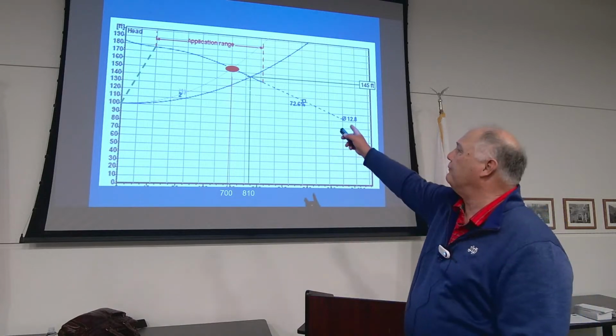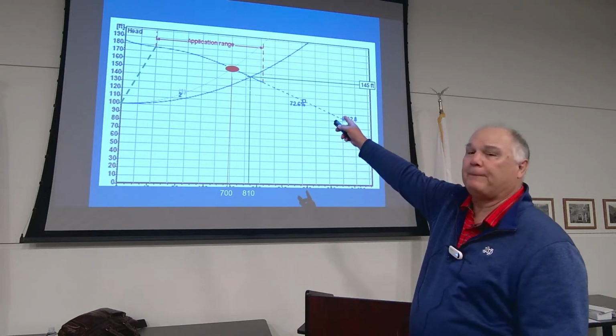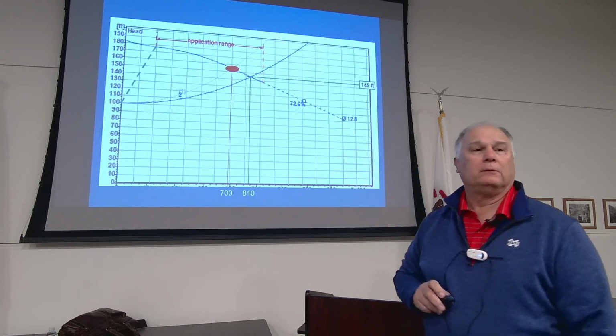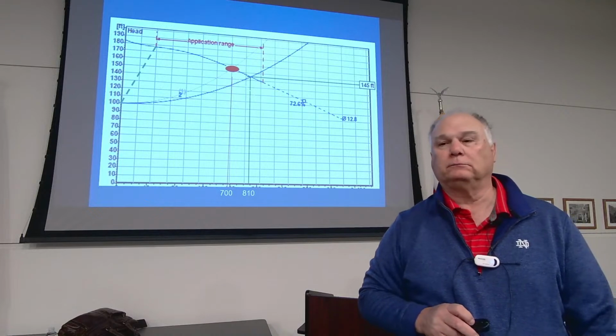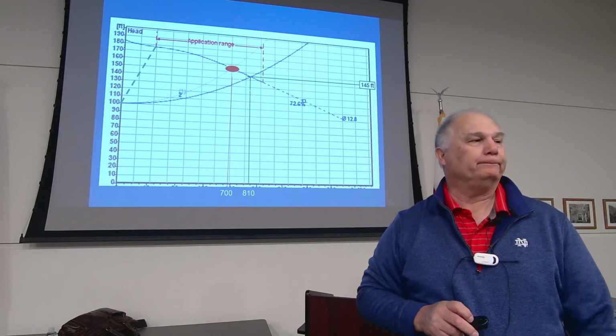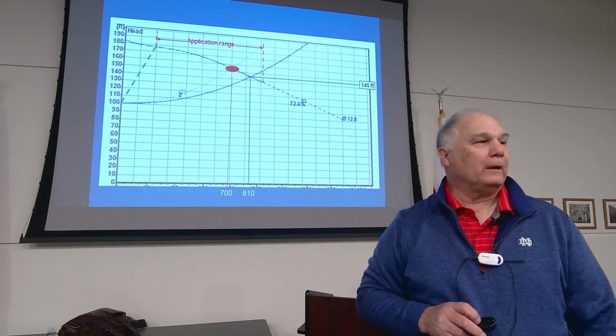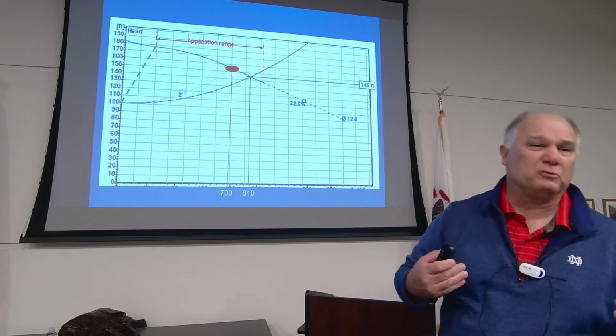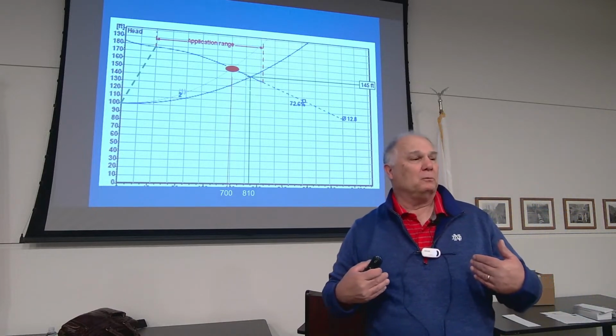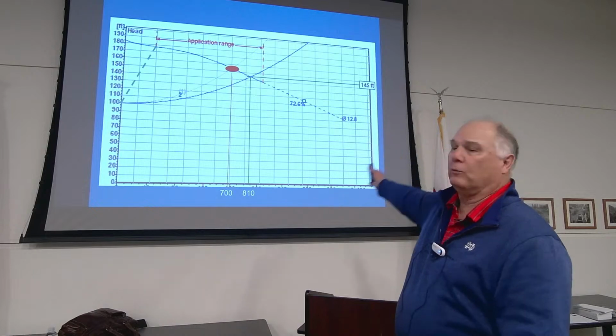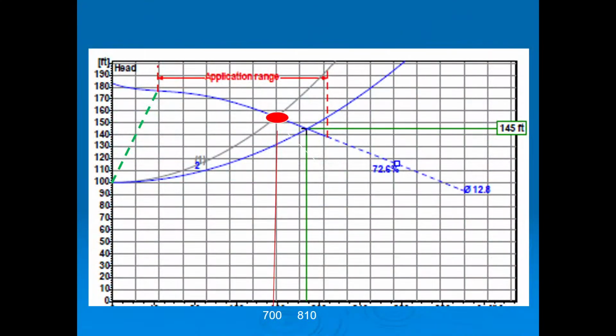If we took a different motor and we had a dash line right behind where that big red dot is, that motor's going to what? Overload. And it will burn up. So what we do as a company is anything less than 20 horsepower or so and down, we just give you that line all the way being blue, solid blue. We call that non-overload throughout the entire curve. Regardless of what the specs say, unless there's a definite need like horsepower limitations or something like that, we want to make sure that regardless of where the station is going to operate, it's going to perform well.